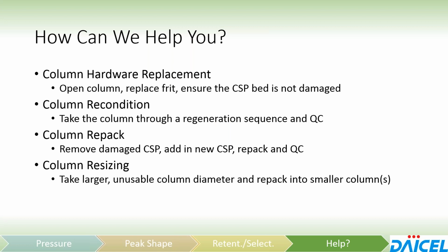Very similar to repack, but we will take it through our regeneration sequence first, make sure that there isn't any analyte that's stuck on there that we can't help get off. And then again, if it needs to be repacked, we will take it into the next step then and do the repack.